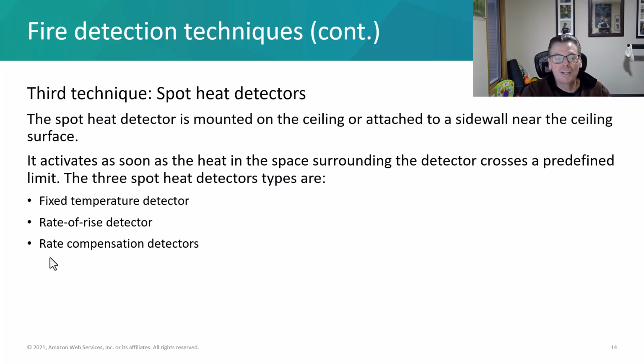The rate of rise detector is going to detect when the temperature in the facility is increasing at an abnormal rate. So it's the rate of change in the temperature over a given period of time. And then we can have rate compensation detectors, which detect fire when the temperature around that equipment reaches a preset value. So that's the temperature surrounding the equipment, whereas the fixed temperature detectors usually activate when a piece of equipment reaches a preset temperature. They kind of do the same thing, but the sensors are located in different locations.